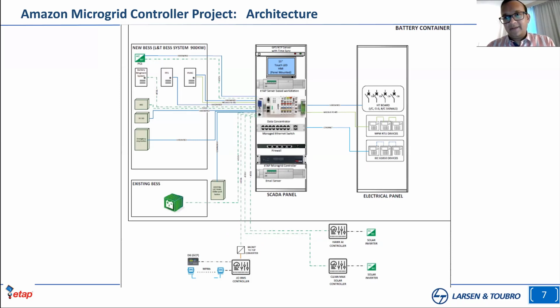This is the battery container architecture which L&T is supplying for this project. On the left hand side is the BESS system, where the battery packs, PLC-based energy management, the PCS, battery energy management system, and ESS controller are all housed in the container for this 900 kW, 900 kWh BESS system. They are hardwired to the data concentrator, and the rest of the architecture is the same as described in the previous slide.